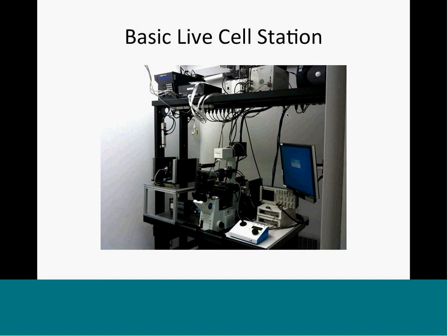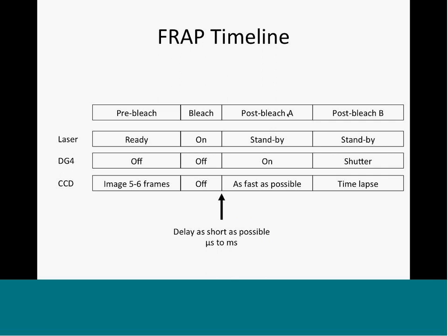One of the types of applications that we support on this microscope, that previously we had tried to support with custom software, was to perform FRAP. The laser in a couple of slides earlier actually comes in as a diffraction-limited point, or a slightly larger diffraction point, and so we're able to perform bleaching at 488 in the optical apparatus. Someone identifies an area they want to bleach, then the stage moves to that particular area, and then the laser fires.